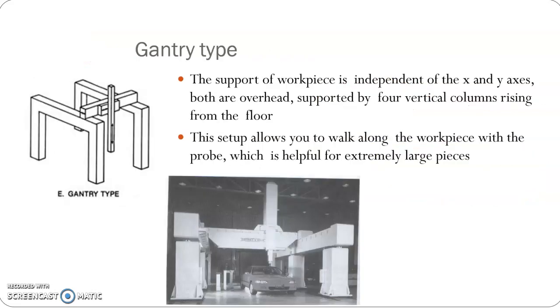In Gantry type, both the X axis and Y axis are overhead, which means we can place large workpieces on the area. Only Z axis is there, so the probe is fixed on the Z axis. The image shows the application of Gantry type CMM.